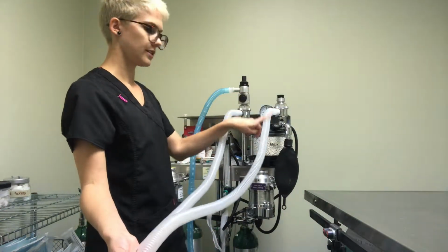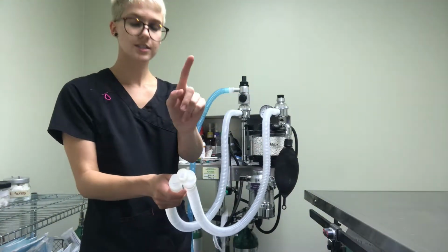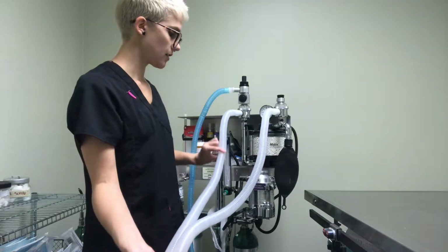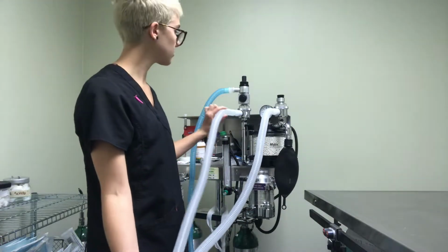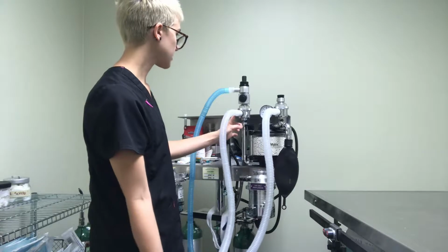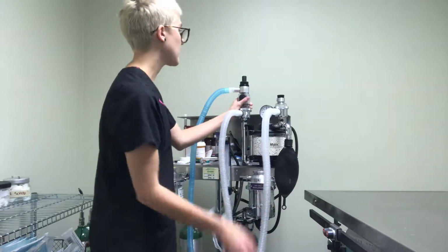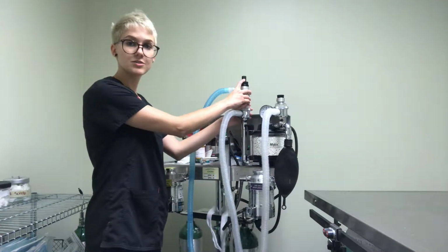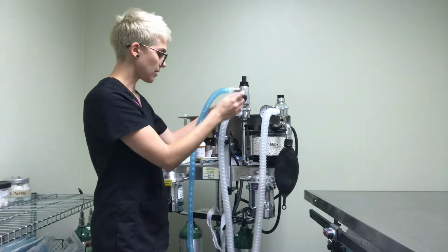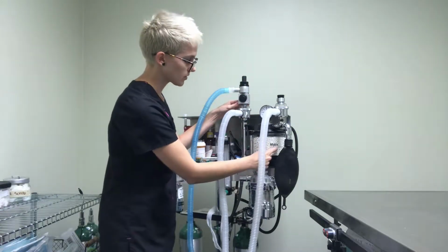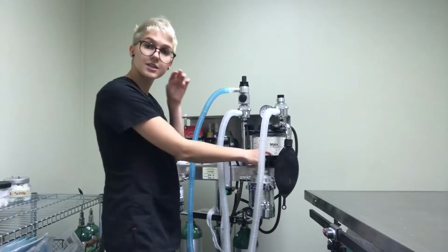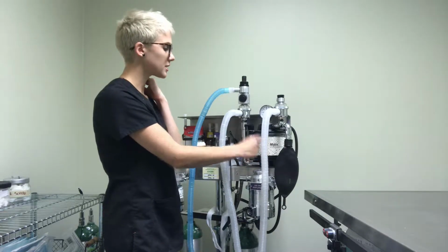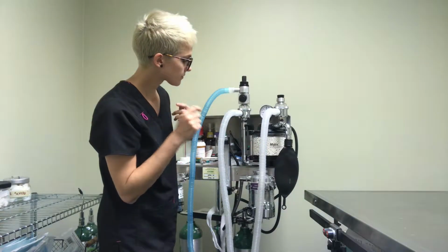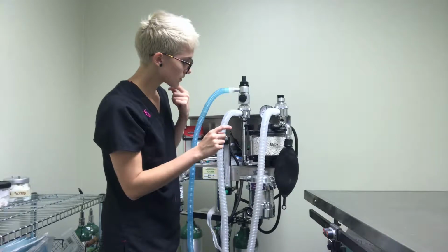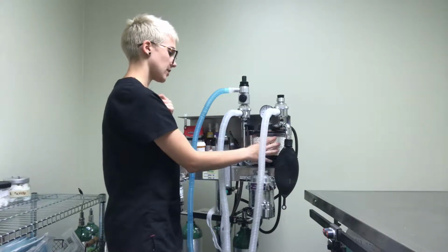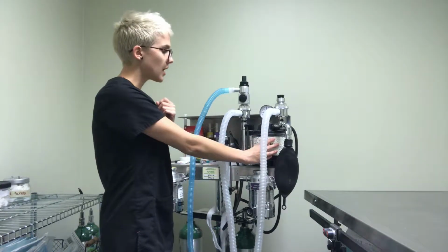These tubes connect to the patient, the E-tube. So it goes out the inhalation valve to the patient, and then from the patient, the waste gas and CO2 come into the exhalation valve. At this point, some of it exits through the pop-off valve. The rest of it goes into the CO2 absorber canister, where the carbon dioxide gets absorbed.